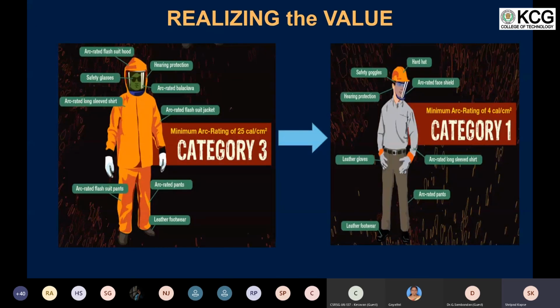If you imagine wearing these two PPEs, this is what a category 3 PPE would look like. So we can understand what kind of suit we may have to wear if we have to work under category 3. On the other hand, since with the arc flash protection we reduced it to category 1, we were able to reduce the category of the PPE, which is much more comfortable to wear and to work in those environments.